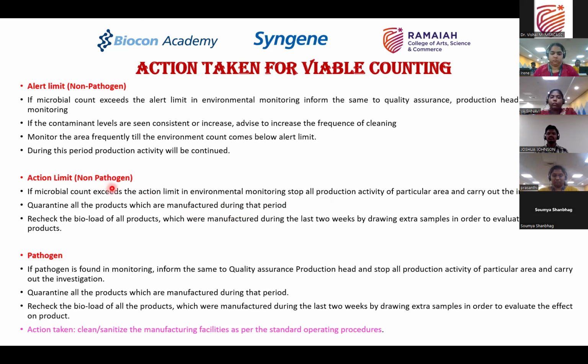Are you getting it, everybody? So there are two levels of this monitoring. One is the alert limit, when the monitoring is happening for viable counts. During the alert limit, production can continue, but the cleaning frequencies and monitoring frequencies have to be increased. But if the viable count is still increasing further and exceeds the action limit, the entire production has to be stopped, and the products manufactured during that time should be quarantined.